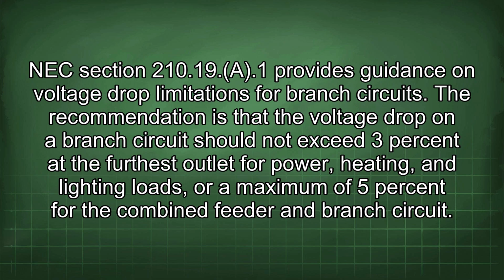NEC Section 210.19(A)(1) provides guidance on voltage drop limitations for branch circuits. The recommendation is that the voltage drop on a branch circuit should not exceed 3% at the furthest outlet for power, heating, and lighting loads, or a maximum of 5% for the combined feeder and branch circuit.